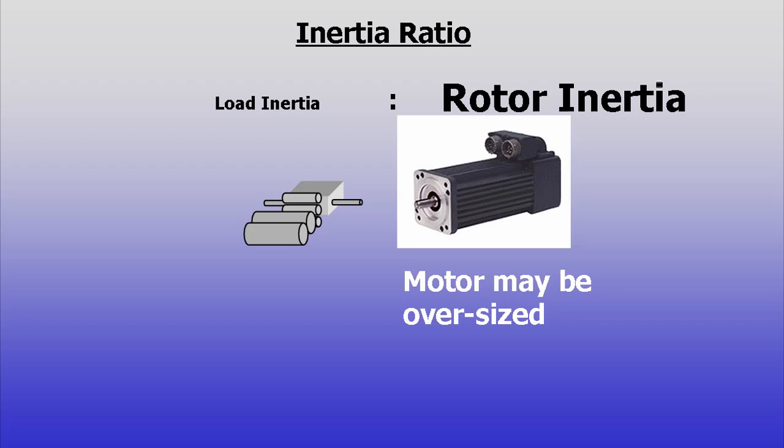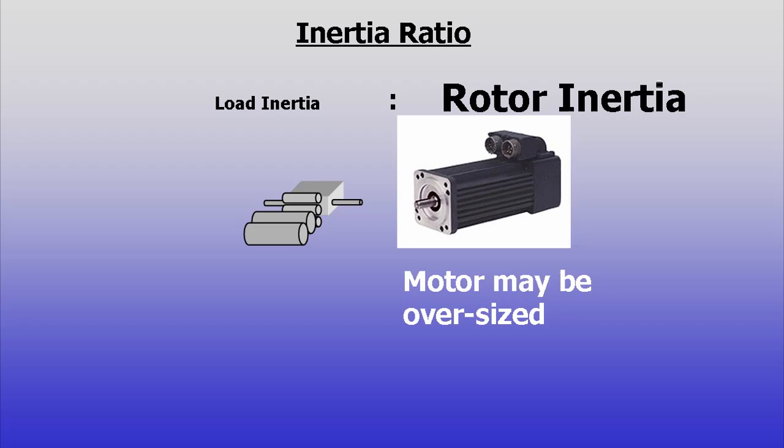Then, it's likely that a smaller motor could do the same job for less cost. Minimum inertia ratios can approach 1 to 1, but rarely need to be lower.